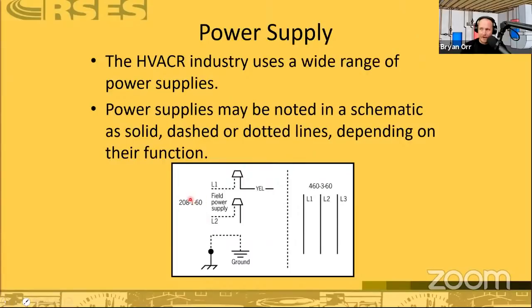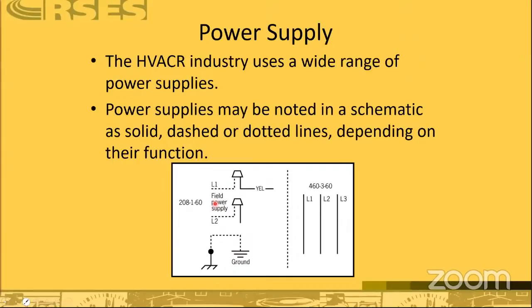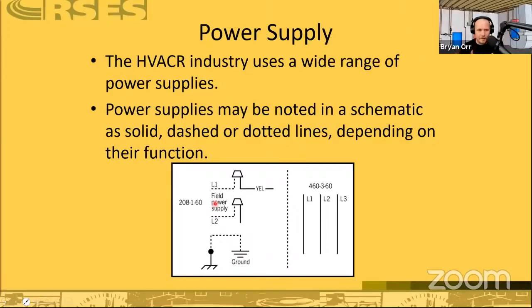You could run into three-phase or single-phase motors. This could say 3, which would mean 3-phase, or it could say 50 hertz. Sometimes you'll run into 50/60, where it could be either. But sometimes you literally have an incorrect product - something not designed for the power supply. It's not common to find a 50 hertz device, but it can happen, especially if you order off Alibaba or somewhere overseas. Sometimes you'll get an appliance or tool that isn't designed for our power supplies, so it's something to watch for. This one here is 460, 3-phase, 60 hertz.